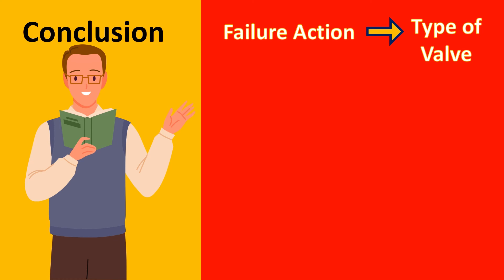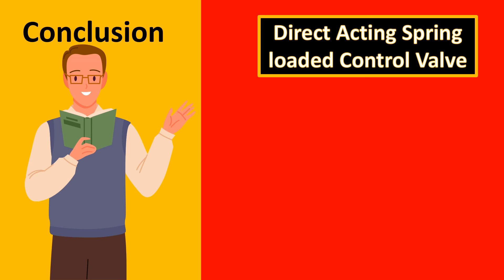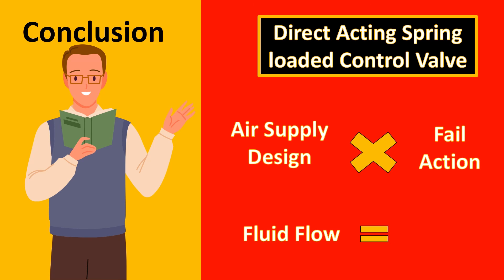Now we look finally into the conclusion of all of these things. The failure action is basically dependent on the type of valve. If it is a direct acting spring loaded control valve remember the air supply always has to be opposite to the failure action, that is air to open for fail close and air to close for fail open. The fluid flow must always assist the fail direction.